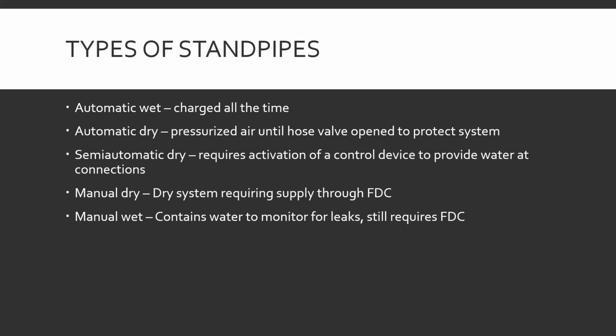Manual dry. Dry system requiring supply through the FDC. These standpipes have no water in them. The only way that you're getting water out of these standpipes is for the fire truck to show up, connect to the fire department connection, and put water into the system. That's the only way. Unless the truck is connected to it, there's no water in the system. The manual wet. Contains water to monitor for leaks, still requires fire department connection. Same kind of premise as the dry. It has water in it. The water is only there so that if there's a leak in the system, it'll drip. Someone goes, hey, that pipe is dripping water, get it fixed. Other than that, there's no actual water supply to it, so you still need the fire department connection to get water out of it.